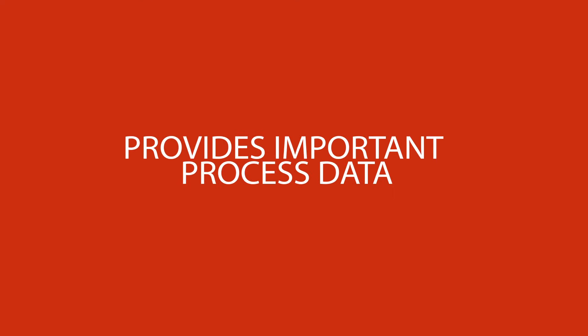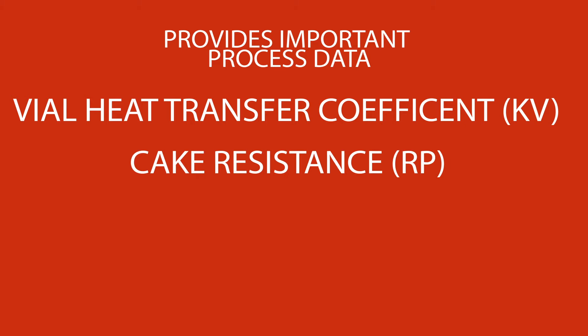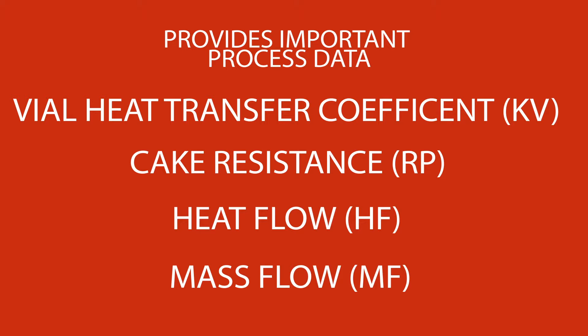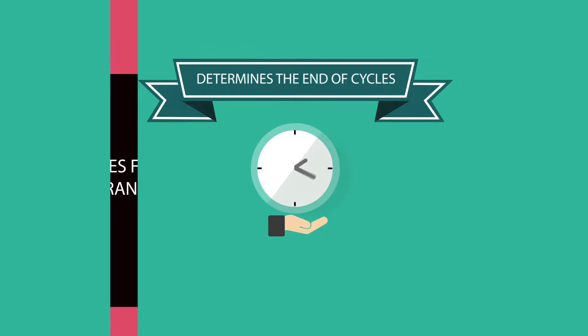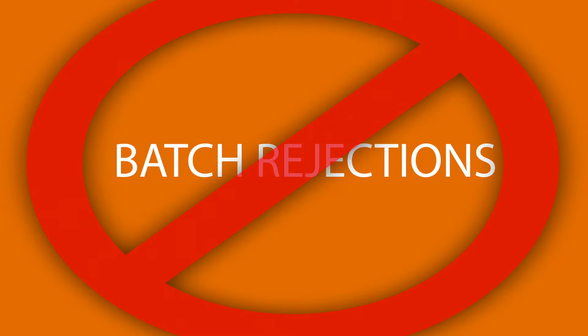What does LyoPAT do? It eliminates the need for thermocouples in vials. Provides important process data such as vial heat transfer coefficient, cake resistance, heat flow, mass flow, and many other significant process parameters. Determines the end of freezing, end of primary drying, as well as end of secondary drying. Enables first-time transfer of protocols between freeze dryers. Ensures repeatable freeze drying processes. Reduces batch rejection.